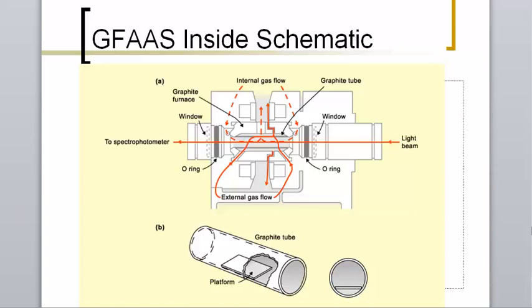The graphite inside view looks something similar to this. The light beam in this diagram starts over to the right or to the right-hand side and it points toward the left-hand side. So the light beam goes through what would be the burner head here in the middle, and then it goes out the other end to the detector. The graphite furnace you see is actually pointed here, and there's a big block that goes all the way around where the burner head would be.